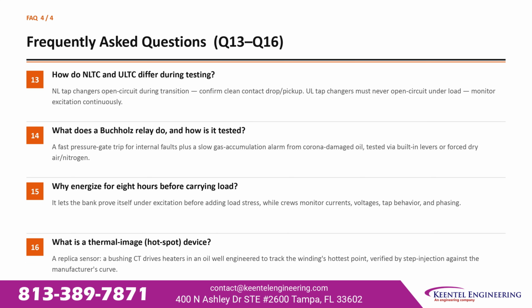How do no-load and underload tap changers differ during testing? No-load tap changers open circuit during transition, confirm clean contact drop and pickup. Under-load tap changers must never open circuit under load. Monitor excitation continuously. What does a Buchholz relay do, and how is it tested? It provides a fast pressure gate trip for internal faults, plus a slow gas accumulation alarm from corona-damaged oil, and it's tested via built-in levers or forced dry air or nitrogen.